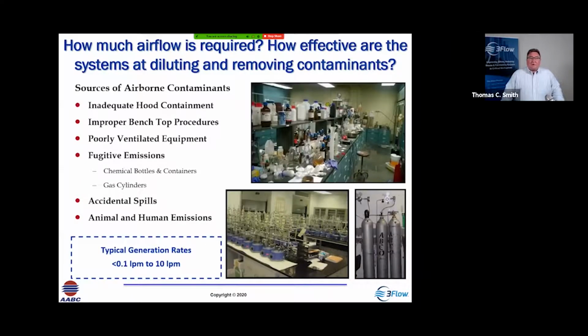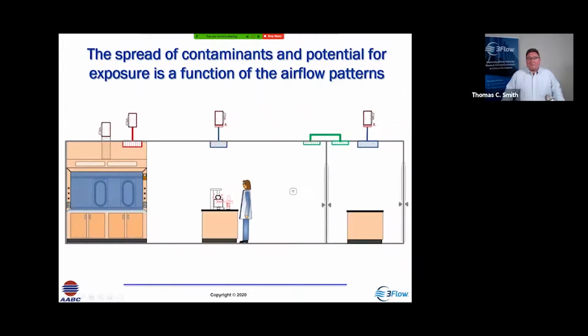Now we also need to know what happens in the lab, as there could be concentrations generated outside of a hood. And so we need to be able to dilute and remove those materials. So typical generation rates, 0.1 to 10 liters per minute. How much airflow is required to protect people?